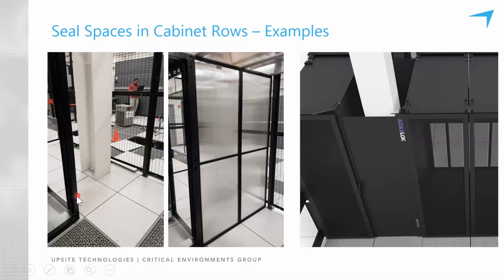It's actually the perfect time to do containment projects. But there's 48 inches and plus a little bit between the edge of that rack and the cage, right? And so you've got the column there. You've got a 24-inch wide space and then the column. So what the customer asked us to do, they required vertical rigid panels, and instead of building one that spans 48 inches wide and the height of the cabinet, there's two of them side by side that are attached to the adjacent panel. And the first one can be removed because this is that roll-in consideration I mentioned earlier, where they would like to in the future be able to roll another cabinet in there, so they can just take this left panel out, put the cabinet in, and reattach the right panel to the end of the cabinet.